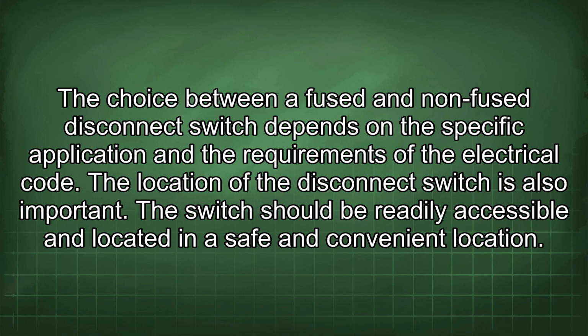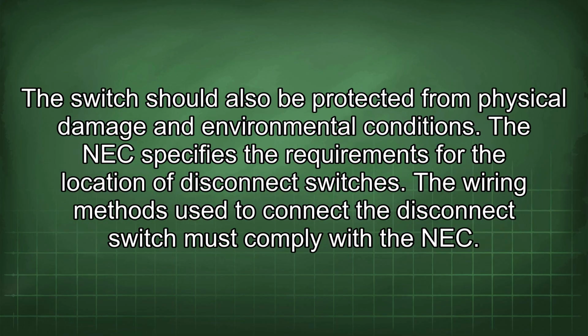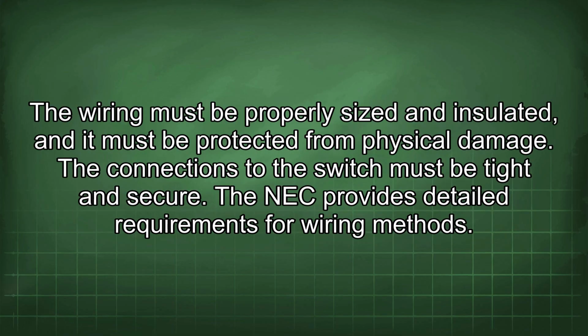The switch should be readily accessible and located in a safe and convenient location. The switch should also be protected from physical damage and environmental conditions. The NEC specifies the requirements for the location of disconnect switches. The wiring methods used to connect the disconnect switch must comply with the NEC. The wiring must be properly sized and insulated, and it must be protected from physical damage. The connections to the switch must be tight and secure. The NEC provides detailed requirements for wiring methods.